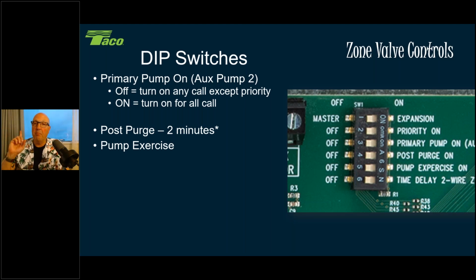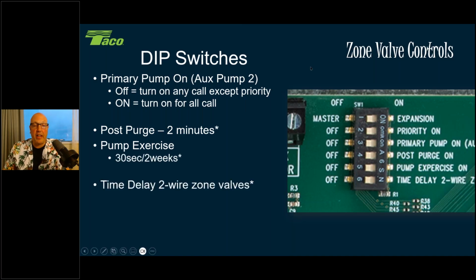So if you're using a zone valve board and using post purge, make sure your indirect tank has a mixing valve on it so the water temperature doesn't get too hot going out to the house. Whoops. And then here you can see that time delay, all right, in the 2-wire zone valves.